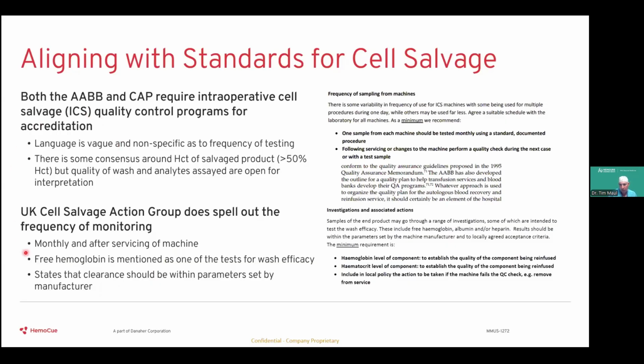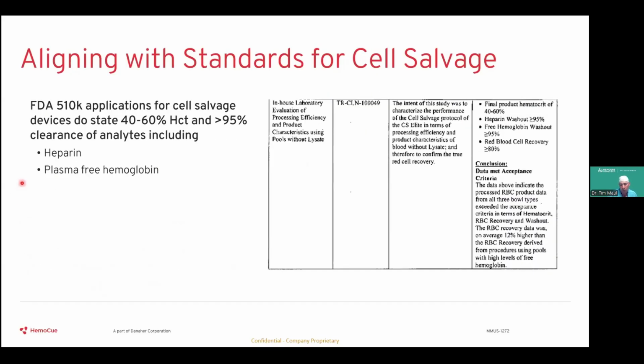So we basically took an approach of combining these two types of guidances to determine that we would look to the FDA's 510(k) applications for the cell salvage device that we're using, to see what they were saying to the FDA that our product should be able to clear from its baseline state. When you look at the 510(k) application, the machine says that it should have a final hematocrit between 40 and 60%, that the heparin washout should be 95% or better, free hemoglobin is being washed out at better than 95%, and a red cell blood recovery between the reservoir and the finished product should be greater than 80%.